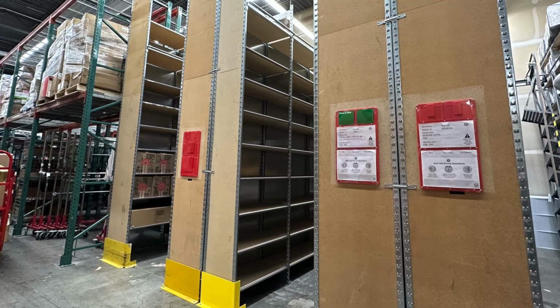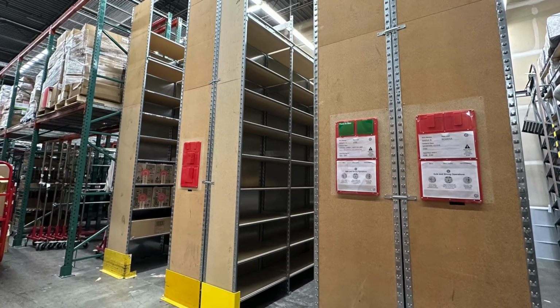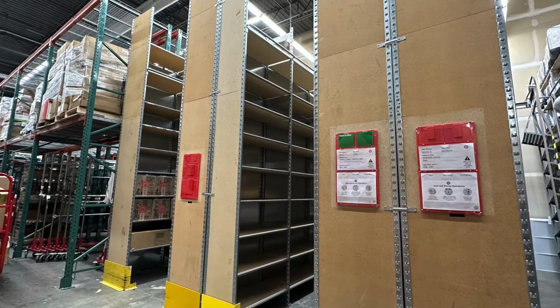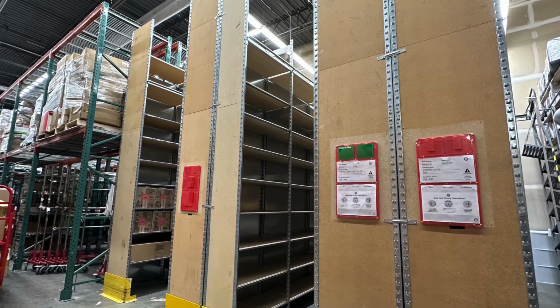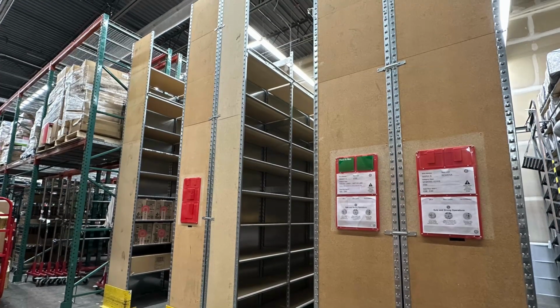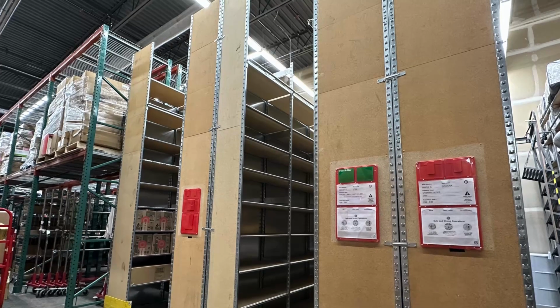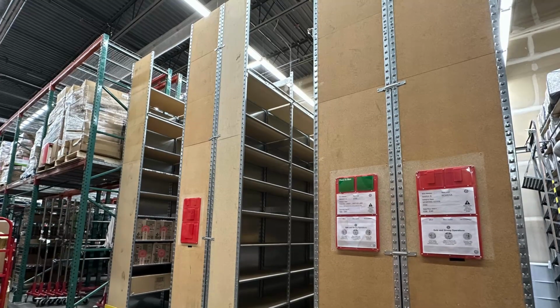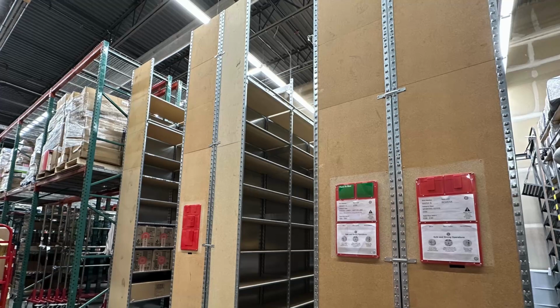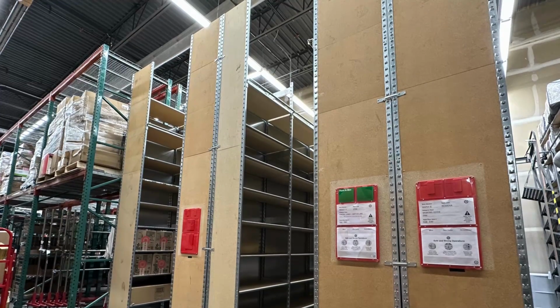We've seen rack storage already. In retail, they also have shelf storage. And that shelf storage, once it gets above 8 feet, is part of a permit process. So you want to make sure that it's not meeting the obstruction requirements for your sprinkler system.